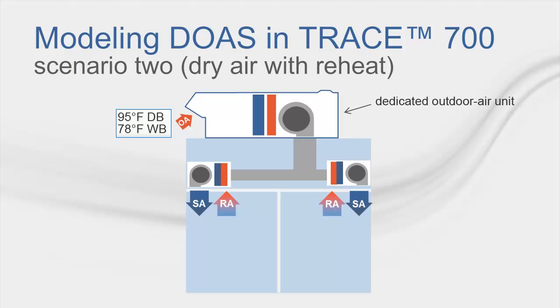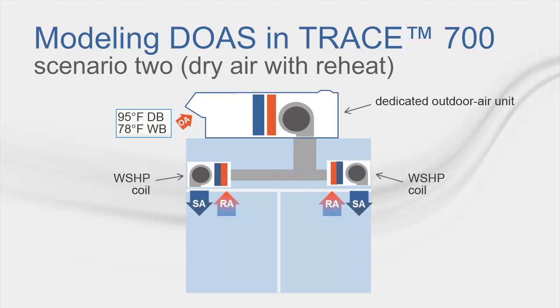For our second scenario, let's consider a building served by water source heat pumps with a DOA that delivers conditioned outdoor air to the individual heat pumps. The conditioned outdoor air from the DOA mixes with the return air before entering the water source heat pumps. During the cooling season, the DOA dehumidifies the outdoor air to a 52-degree dew point and then reheats it to 70 degrees dry bulb. During the heating season, the DOA heats the outdoor air to 68 degrees.